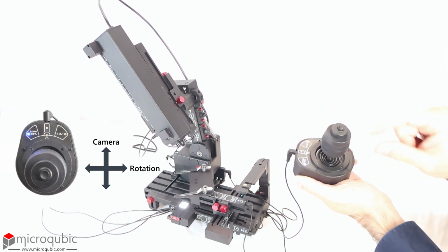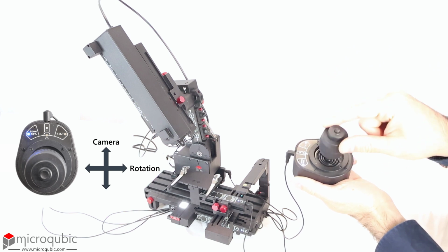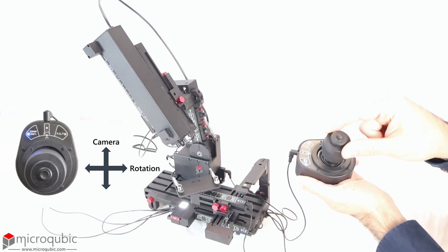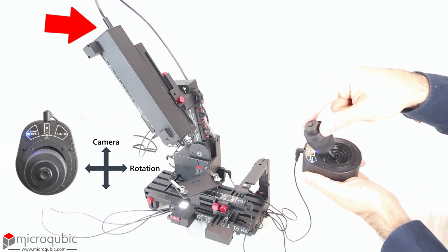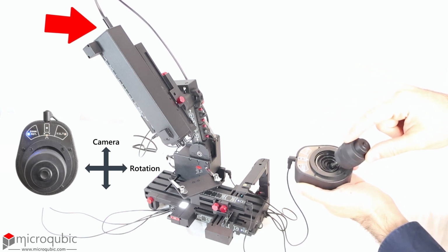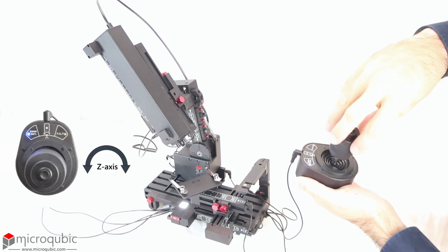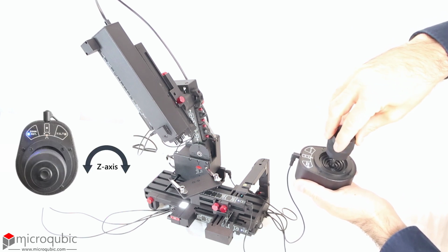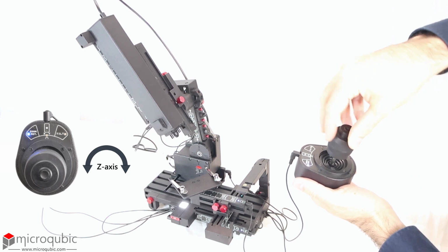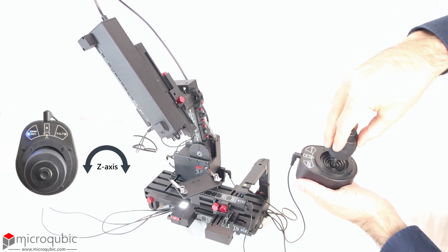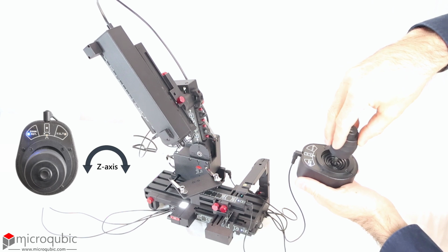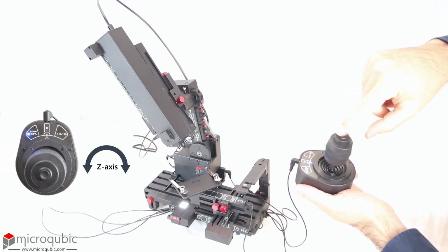Finally, the touch switch on the left activates the mode where left-right movement controls the sample rotation, and up-down controls the camera axis, effectively changing the zoom level. In every mode, rotating the knob clockwise or counterclockwise controls the Z-axis to adjust the focus.